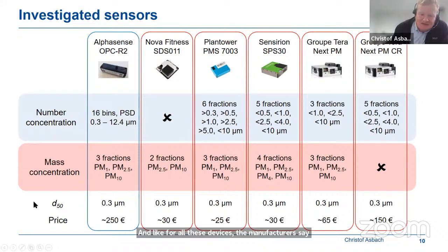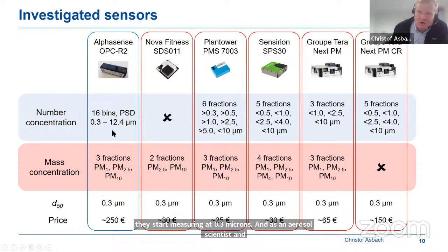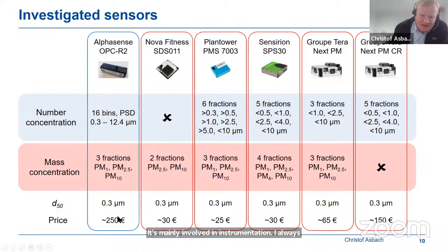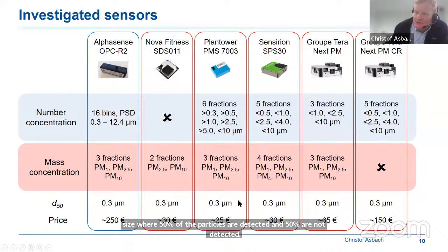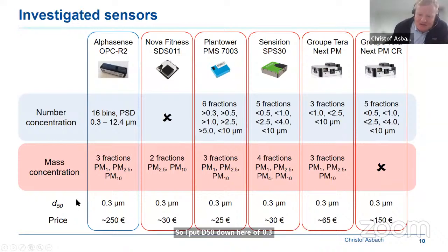And as an aerosol scientist mainly involved in instrumentation, I always interpret the lower detection limit as a D50. That is the size where 50% of the particles are detected and 50% are not detected. So I put a D50 down here of 0.3 microns. We will see in a bit that this is kind of a misunderstanding on my side, or maybe the manufacturer's side, I don't know, on what the lower size end actually means. So this gives size distribution in 16 size bins and PM1, PM2.5, and PM10 mass concentrations.